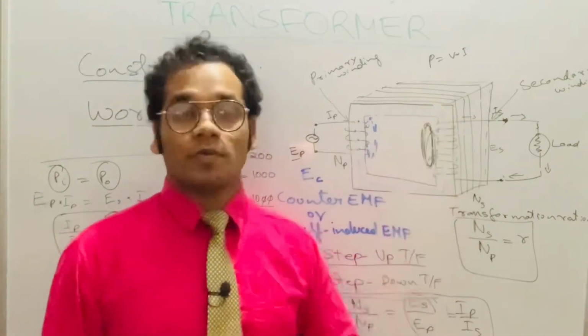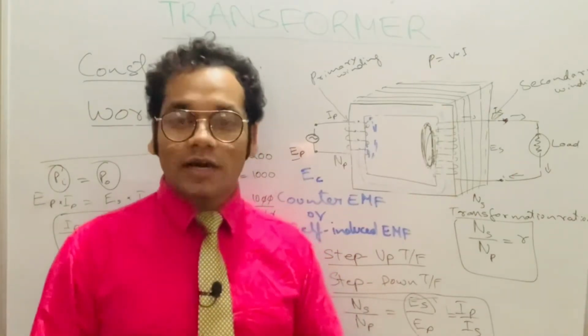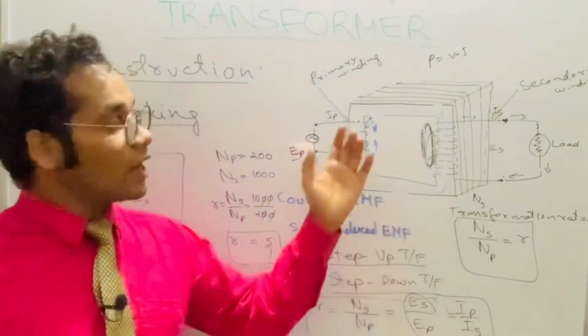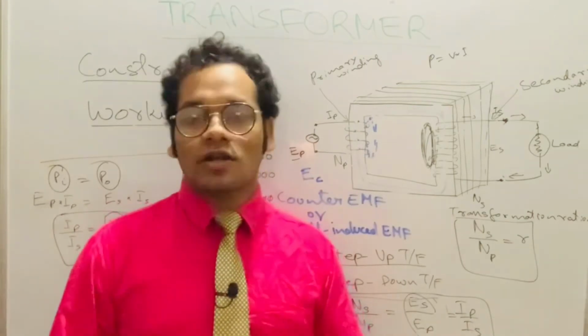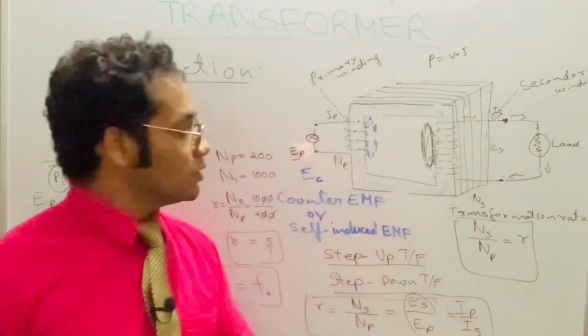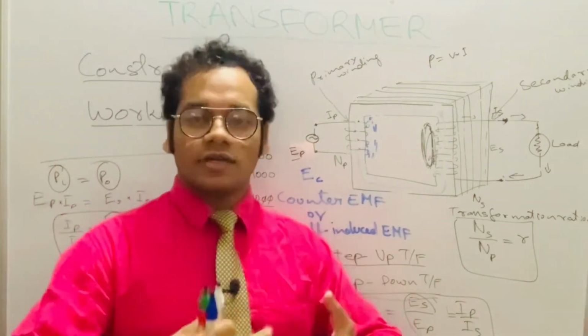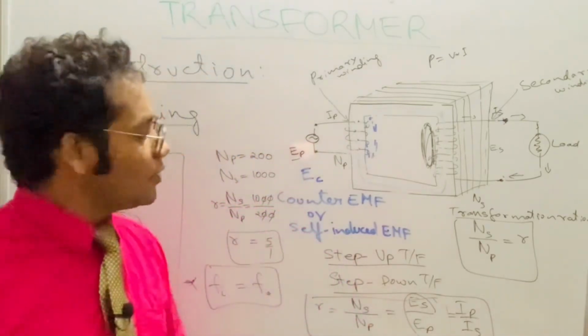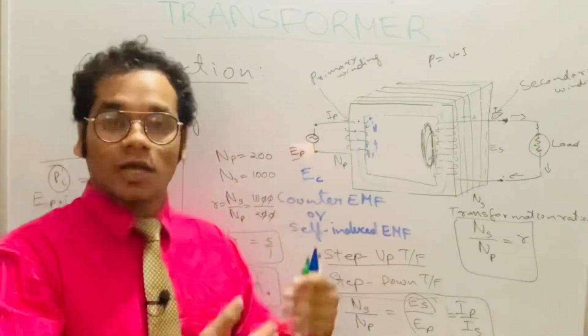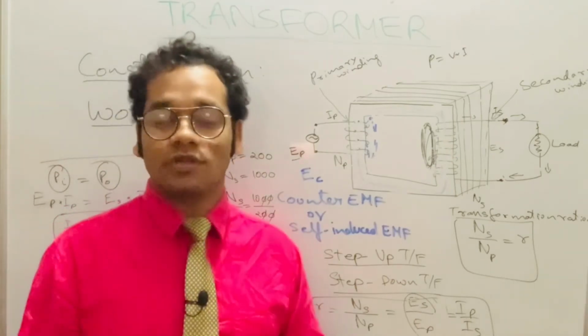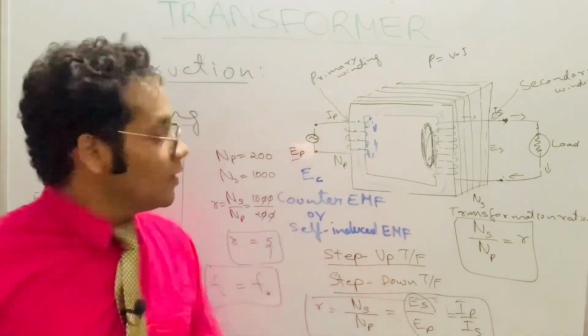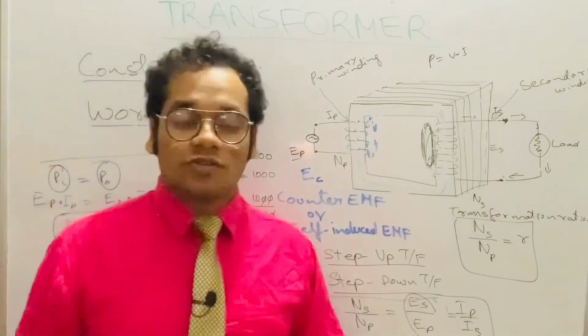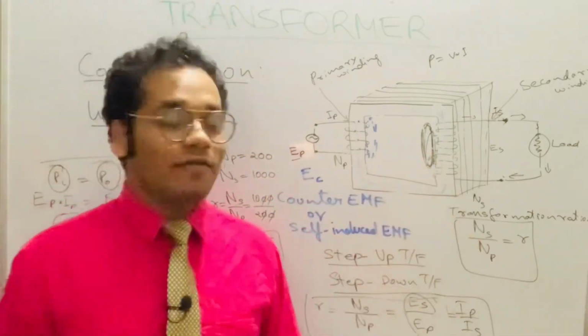This core has properties of high permeability and low reluctance, because of which we have less eddy current loss and hysteresis loss. Both are minimized. It is made of stampings or laminations, with thickness of 0.30 or 0.35 mm. For a 50 Hz transformer, the thickness can be 0.35 mm.